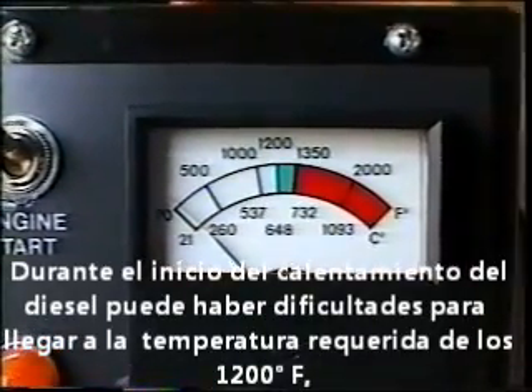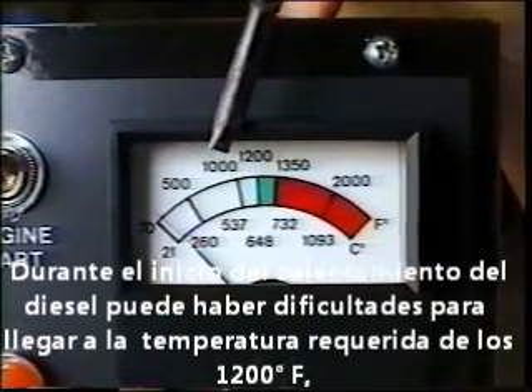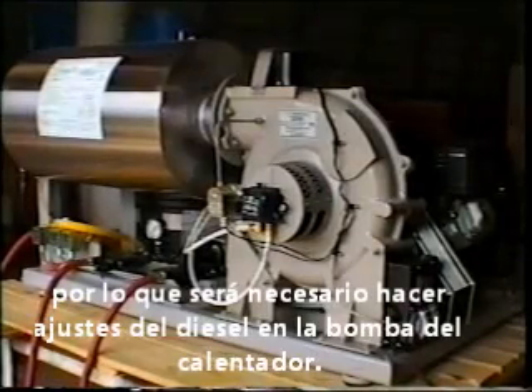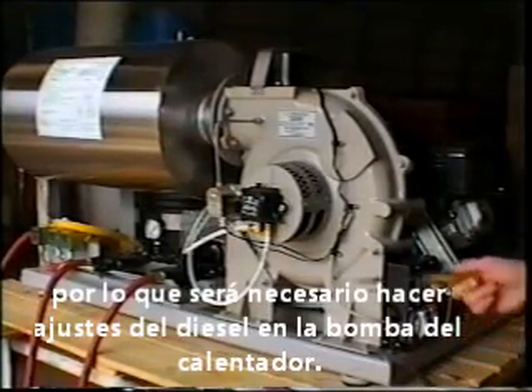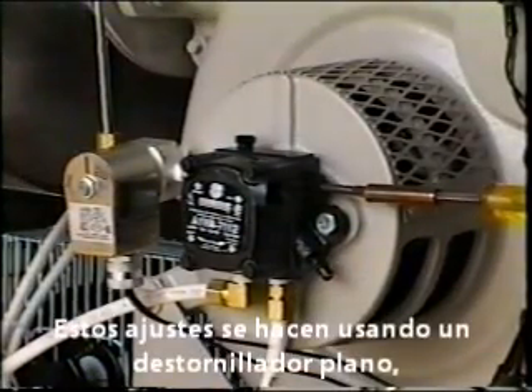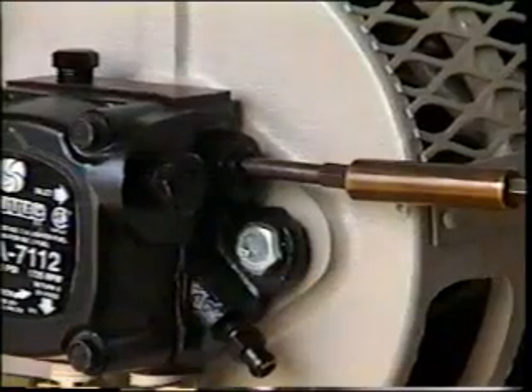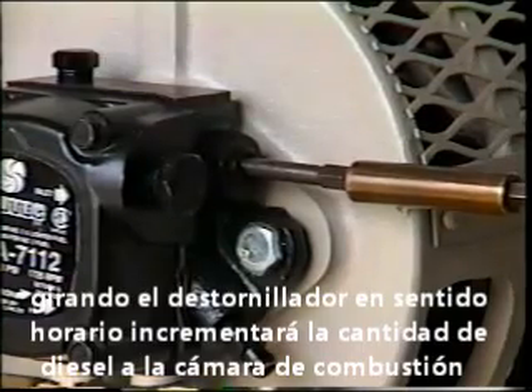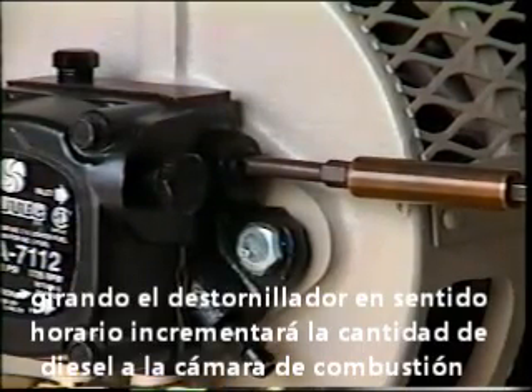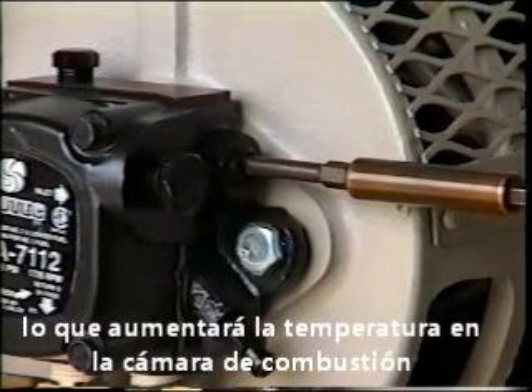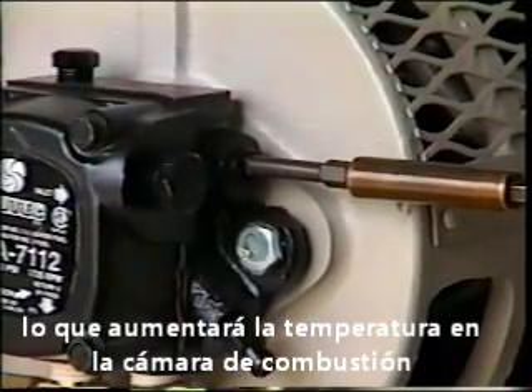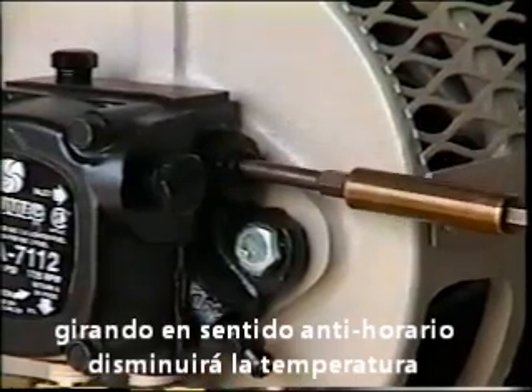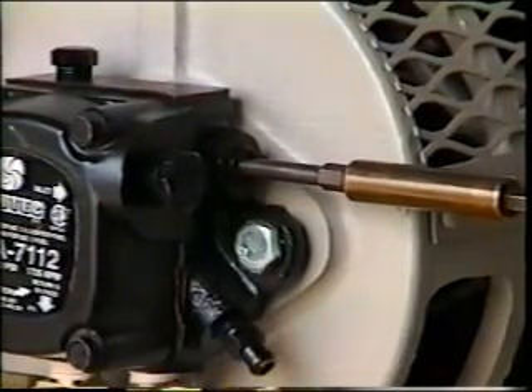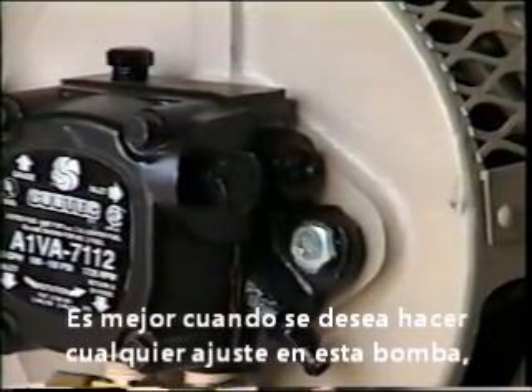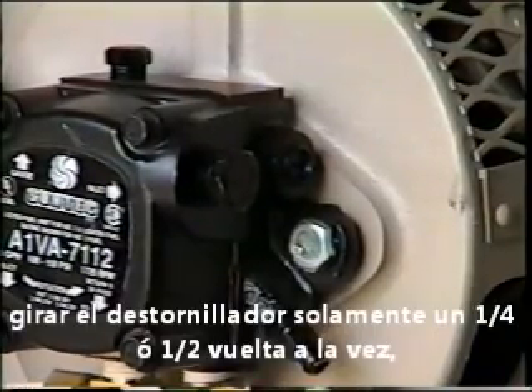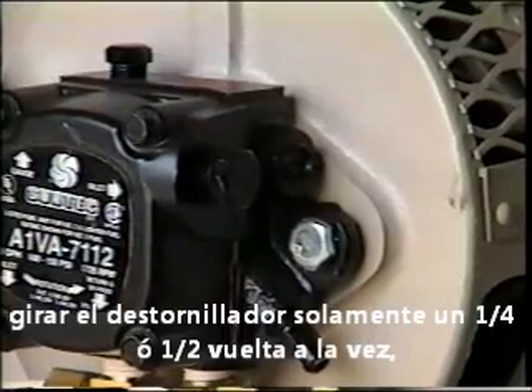During the initial warm-up period, if you are having difficulty reaching the required temperature of 1200 degrees, it may be necessary to make an oil feed adjustment on the oil burner pump. This adjustment is made by using a flat blade screwdriver. By turning this adjusting screw in a clockwise direction, this will increase the amount of oil going to the combustion chamber, which will increase the temperature in the combustion chamber. By turning it counterclockwise, you can decrease the temperature. It is best when making any type of adjustment on this pump to only turn the screw about 1/4 to 1/2 of a turn at a time.